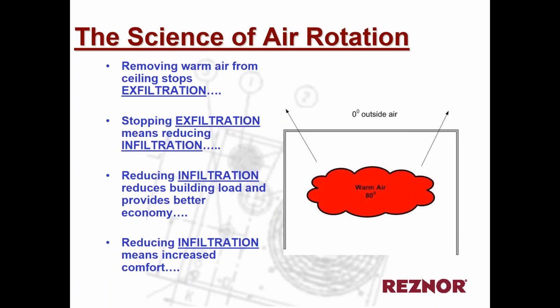So the air turnover unit does a very good job of moving that air, preventing exfiltration and infiltration, and it gives you a good temperature gradient from the ceiling to the floor of about 2 to 3 degrees. So up in the ceiling deck it would be maybe 73 degrees, and down at the floor where people are, it is typically about 70 degrees.